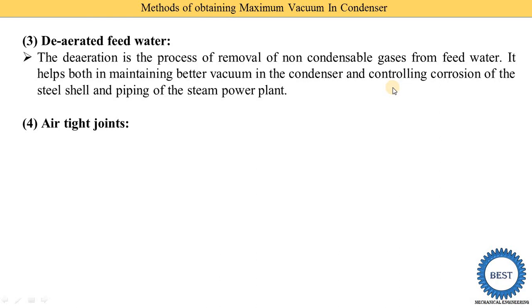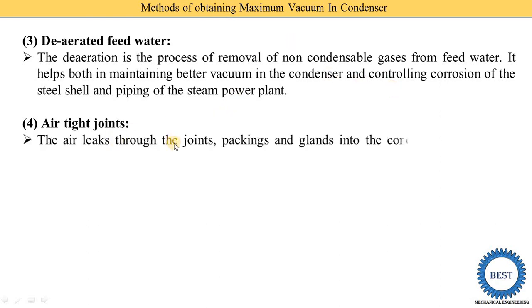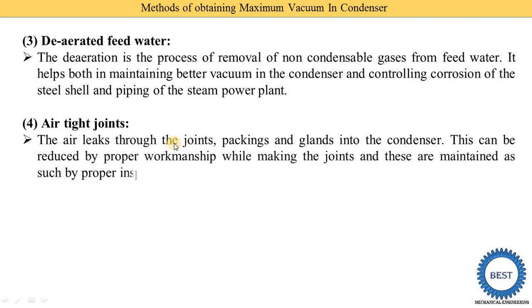The fourth method is airtight joints. In a condenser there are various joints, and we need to make these joints airtight so that air does not enter from the atmosphere into the condenser. Air can leak through joints, packings, and glands into the condenser. These leaks can be reduced by proper workmanship while making the joints, and maintained by proper inspections from time to time to check for air leakage from various joints.